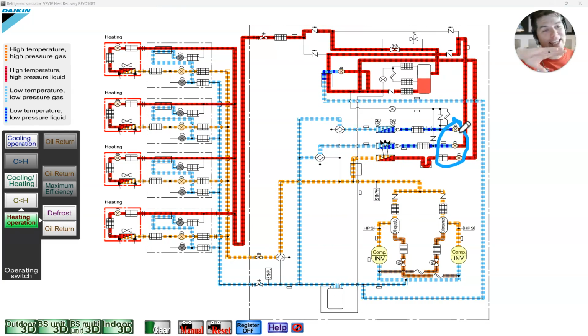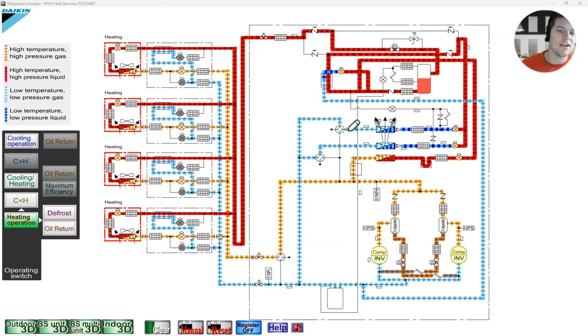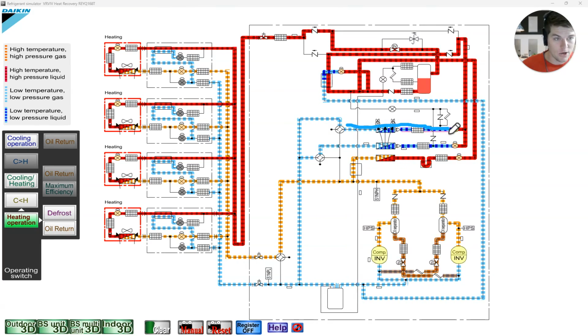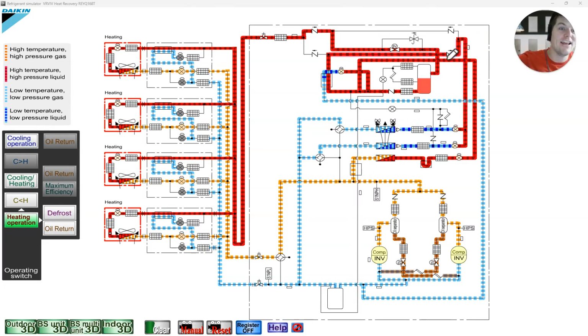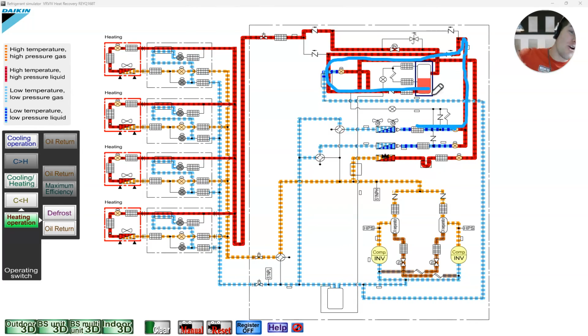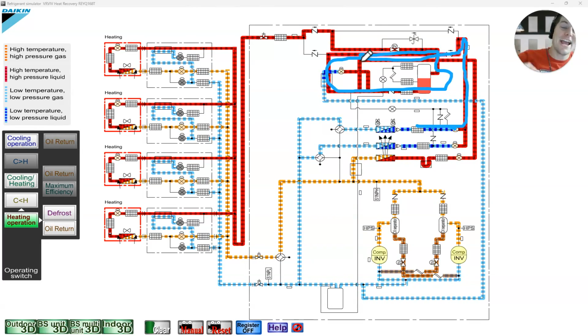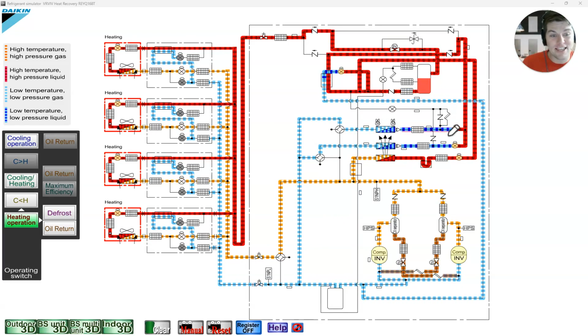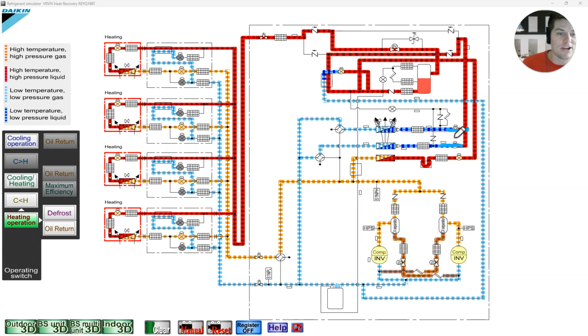I'm not getting enough. So what happens? This line is a suction line and it's supposed to be saturated liquid, but it's just vapor now. This is wide open, so we're not metering it. So guess what? It goes up the line and it goes across and back over, back to my liquid receiver. And guess what? All of that blue is now in a low pressure state because this is wide open. This is not metering any refrigerant.